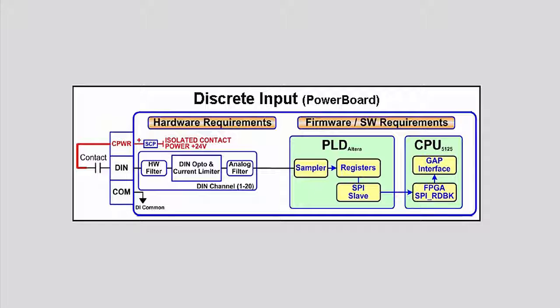The contact output power on pins 21, 22 and 23 can supply up to 150 milliamp maximum. If desired, an external 16 to 32 volt DC power source can be used for the circuit wetting voltage.